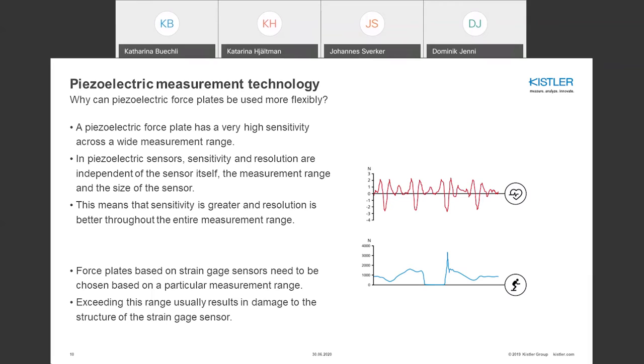Regarding the wide measurement range: in piezoelectric sensors, sensitivity and resolution are independent of the sensor size and measurement range. You can measure with the same force plate both standing heartbeat and dynamic movements like a countermovement jump. With strain gauges, you are bound to a specific measurement range, and exceeding it usually results in damage to the sensor structure. With piezoelectric force plates, you can't really destroy the sensor — only potentially the mechanical parts of the force plate.